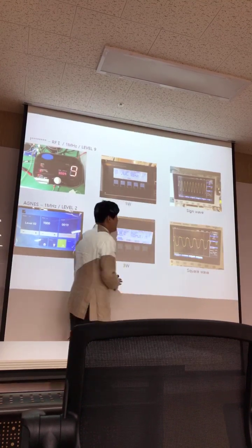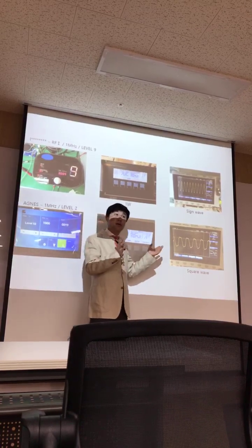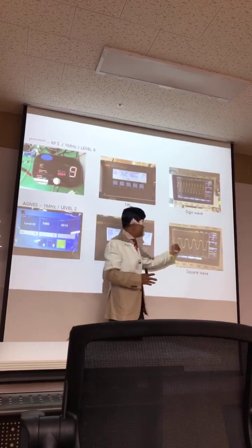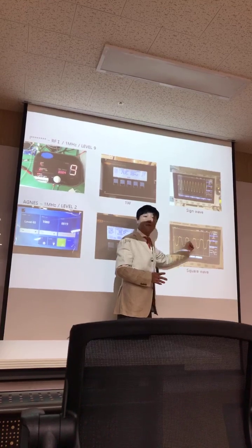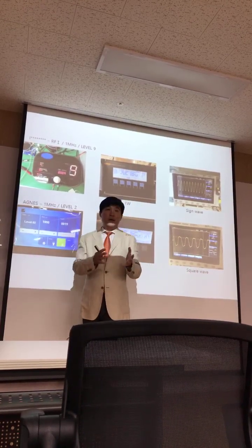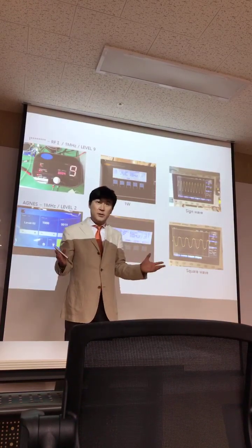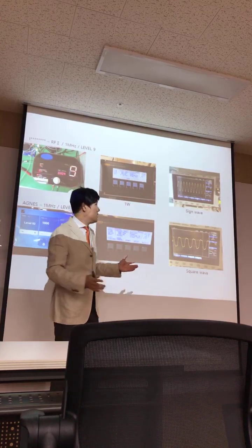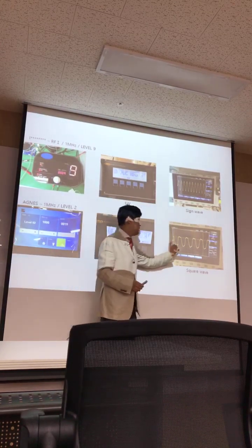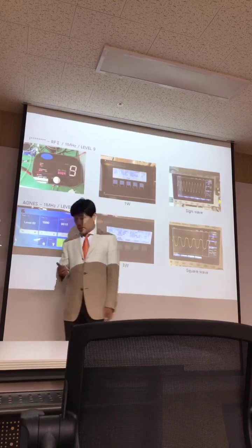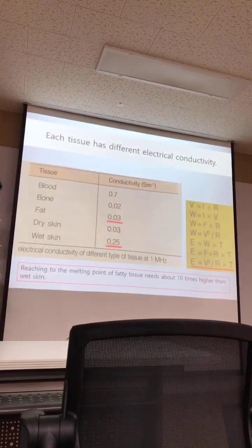It's the same as in laser treatment. This kind of flat top waveform can minimize the surrounding thermal tissue damage. That's why we made this shape of waveform.